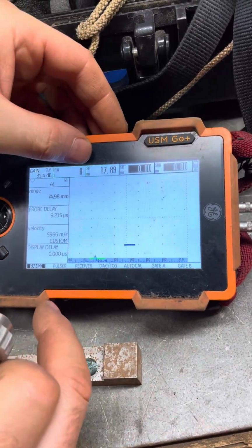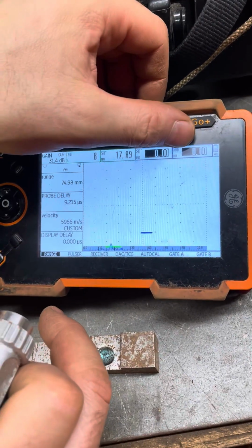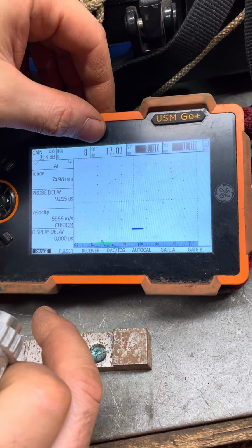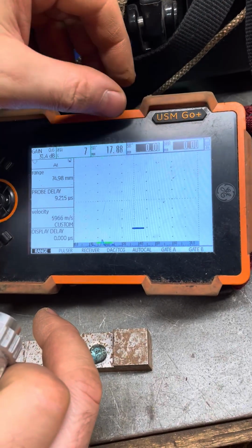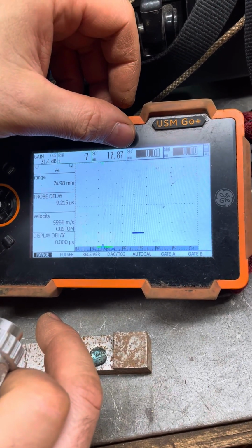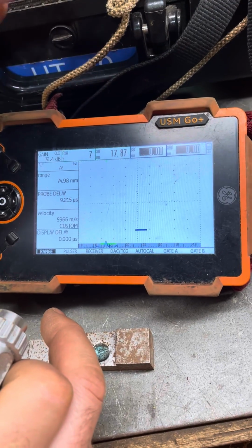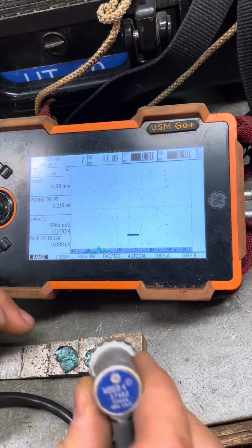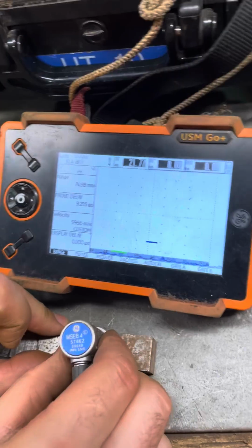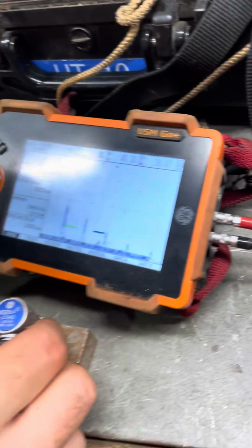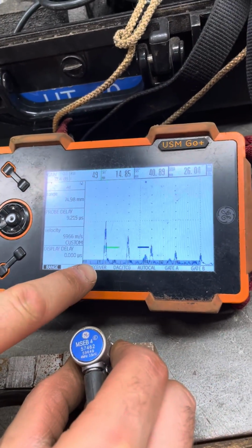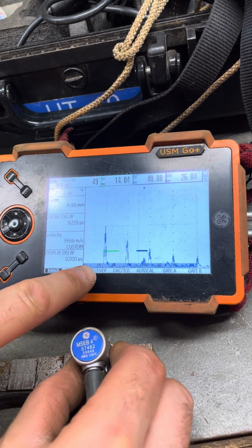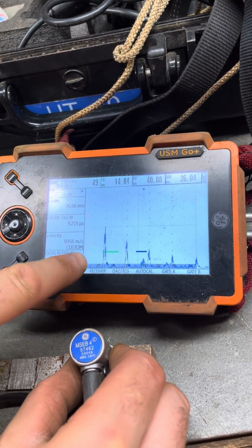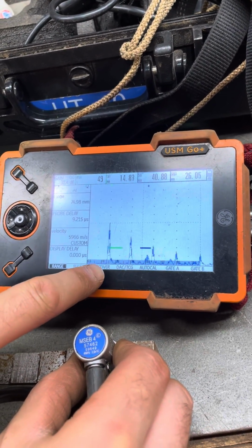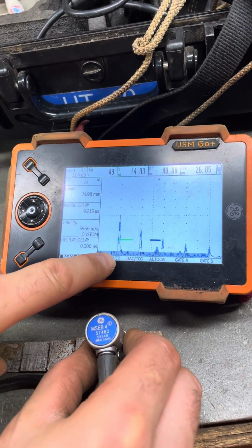Here, as I mentioned, with A it shows CA, CB, and the difference without paint. The first signal, the second signal, and without paint, the second signal will be longer, because it goes back and forth, while the first ones just go back and forth. Now we set it to 15, and then down below, you can clearly see that we now have 0, 10, and 15 displayed. It immediately and accurately shows the value of 15. Here it matches up, it is 15, exactly 15. At the bottom it's 15 millimeters, it even shows it at the bottom.